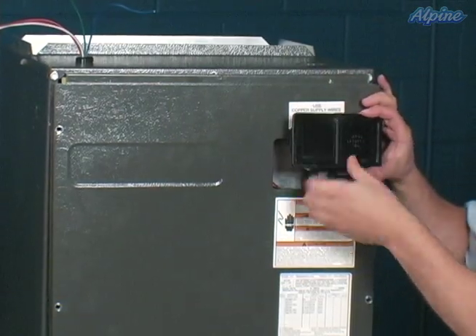And this little plate has a knockout that can be cut. If you have a single breaker, then you cut out half the knockout. If you have a double breaker, such as with the larger 20 kilowatt heater coil, then you cut out both of these.